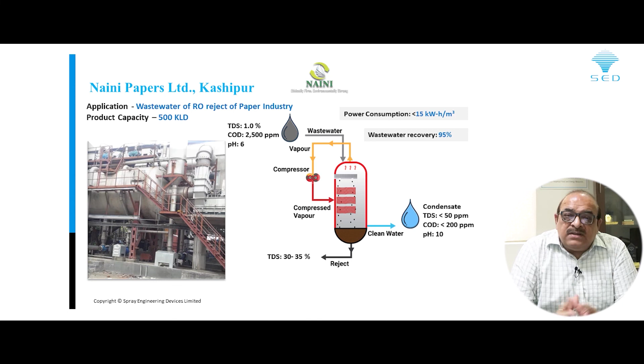This plant has been working for the last 2 to 2.5 years. We are getting a TDS of less than 50 ppm sometimes, a very pure kind of water, recovering more than 95% with a nominal power consumption of less than 15 kilowatt hours per cubic meter of feed.